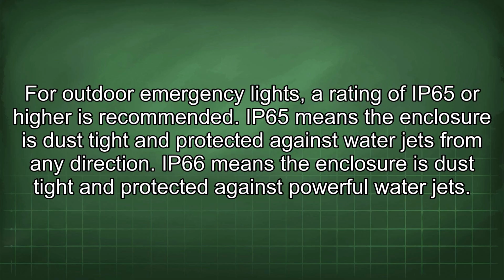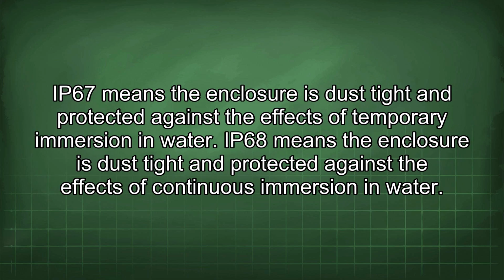IP65 means the enclosure is dust-tight and protected against water jets from any direction. IP66 means the enclosure is dust-tight and protected against powerful water jets. IP67 means the enclosure is dust-tight and protected against the effects of temporary immersion in water. IP68 means the enclosure is dust-tight and protected against the effects of continuous immersion in water.